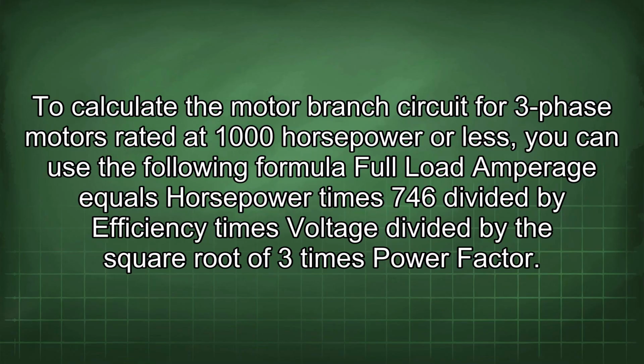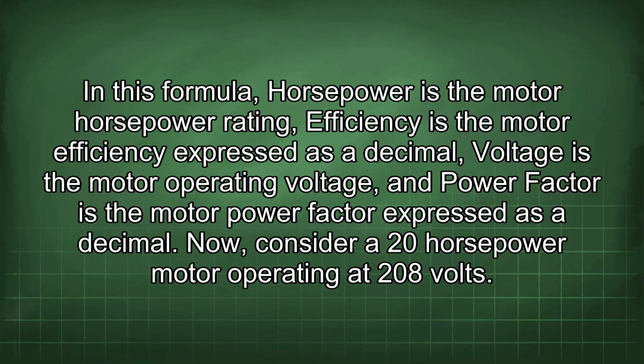To calculate the motor branch circuit for three-phase motors rated at 1000 horsepower or less, you can use the following formula: full load amperage equals horsepower times 746 divided by efficiency times voltage divided by the square root of 3 times power factor. In this formula, horsepower is the motor horsepower rating, efficiency is the motor efficiency expressed as a decimal, voltage is the motor operating voltage, and power factor is the motor power factor expressed as a decimal.